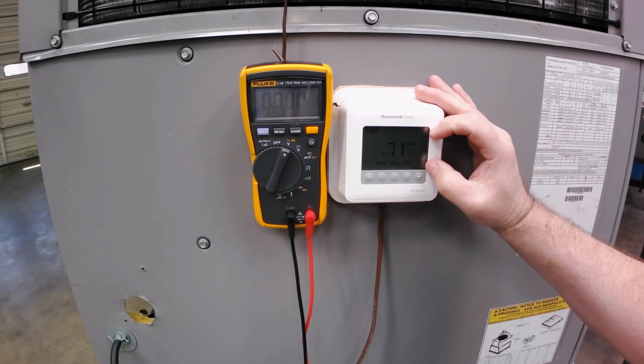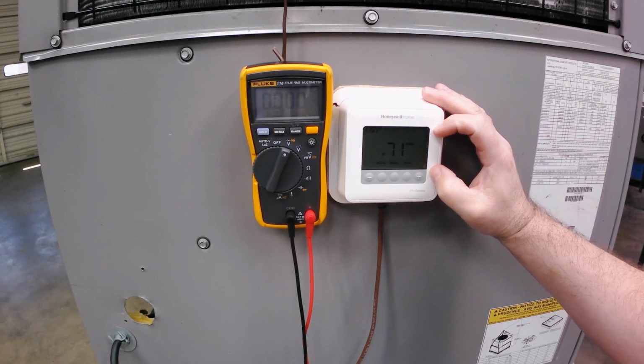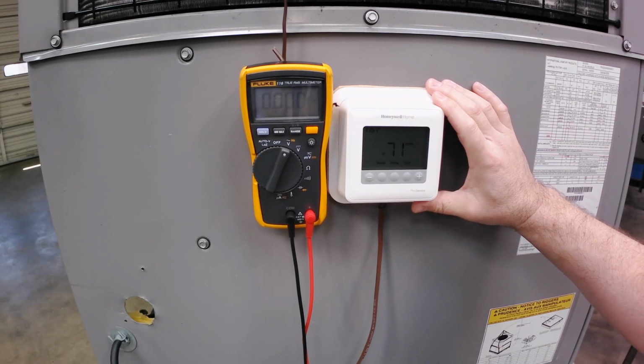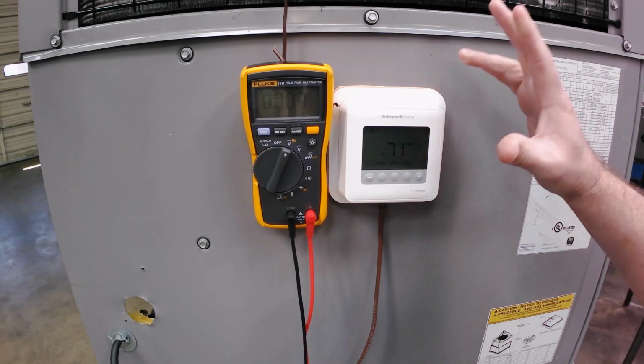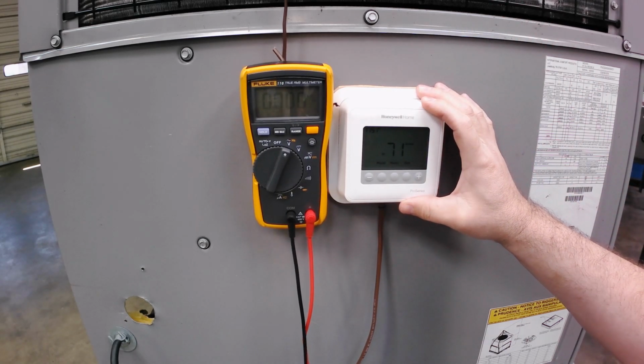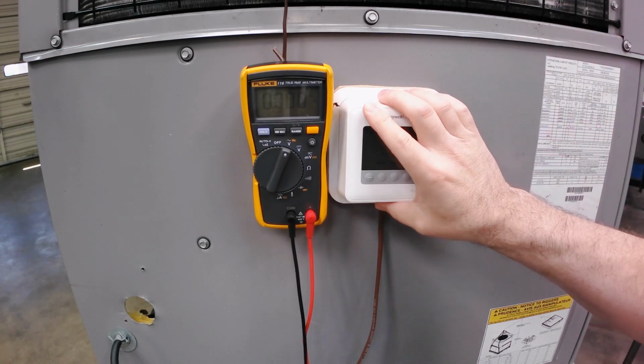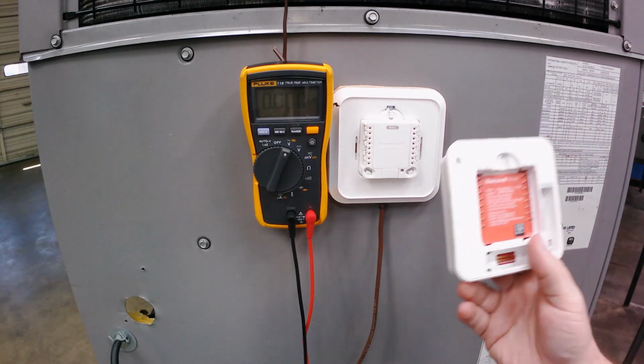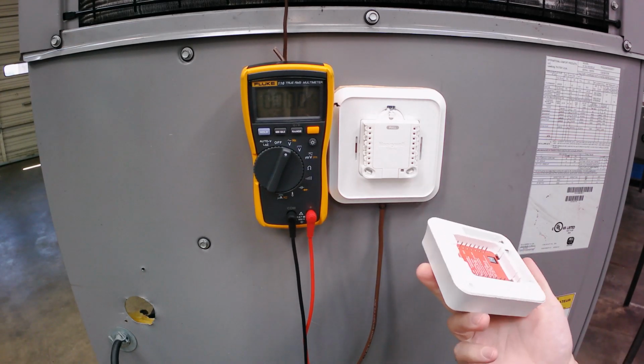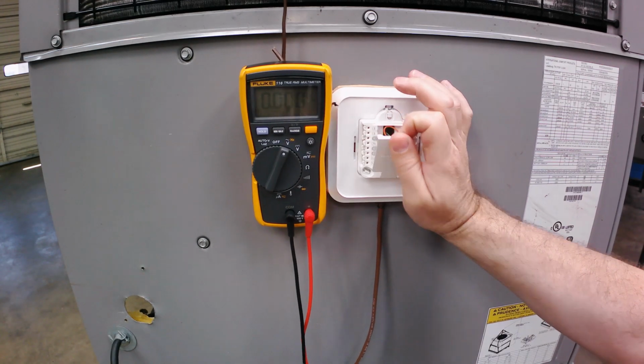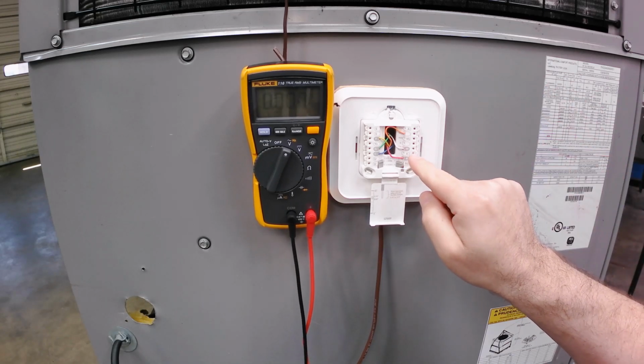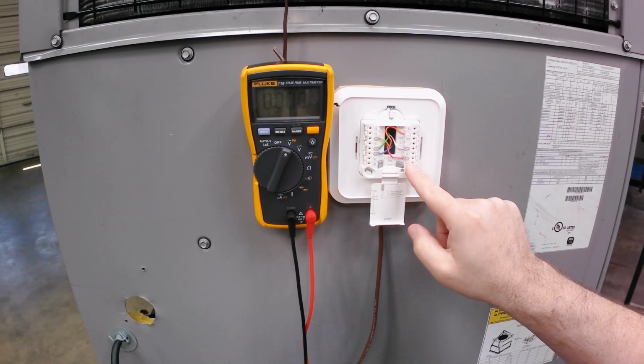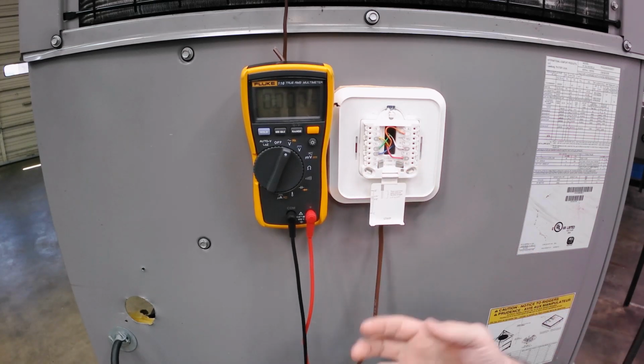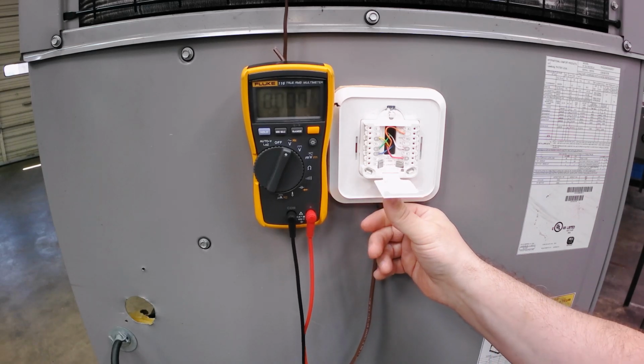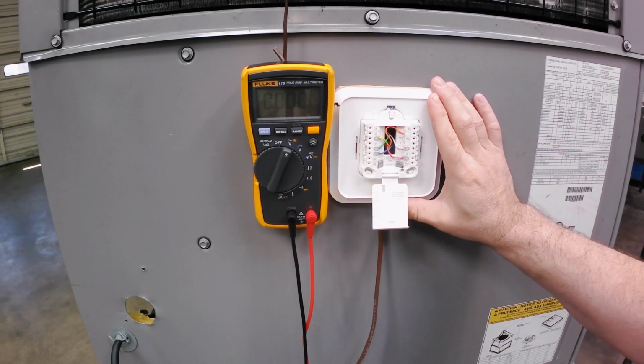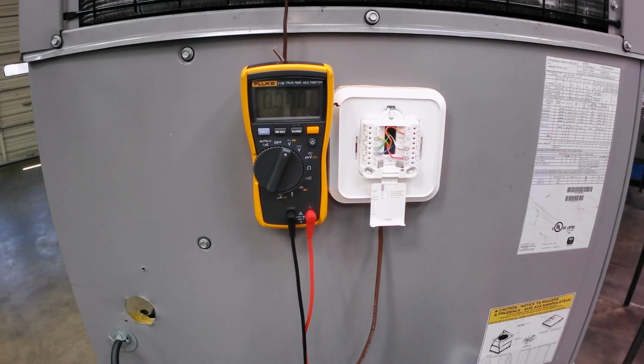Just because you see the screen lit up doesn't mean you actually have power on R or R and common. If you check the total power supply, you could have batteries in the system. So if it's blank because of a float switch, bad transformer, or whatever, don't assume anything. Take your cover off, make sure you don't have batteries, and then do a simple voltage check. For me, I tell the guys I come across, the only thing you can check on this subbase is for power. If you know you have power there, that is about as good as you need it to get, because checking voltage to any other thing is probably going to confuse you.